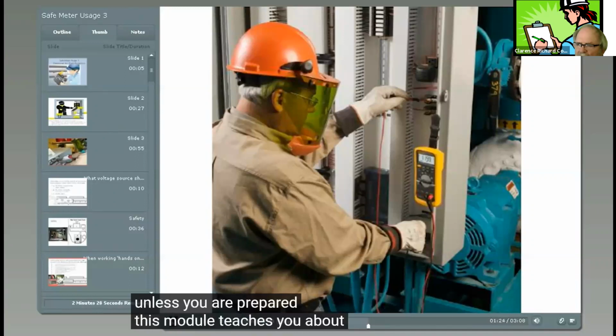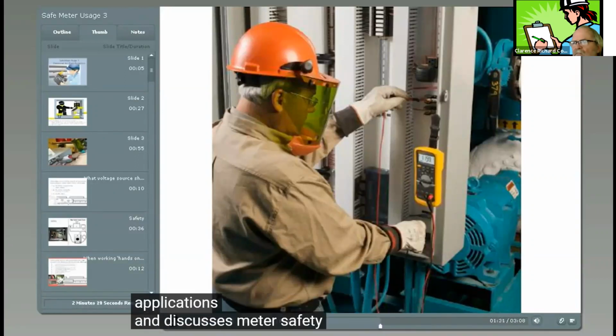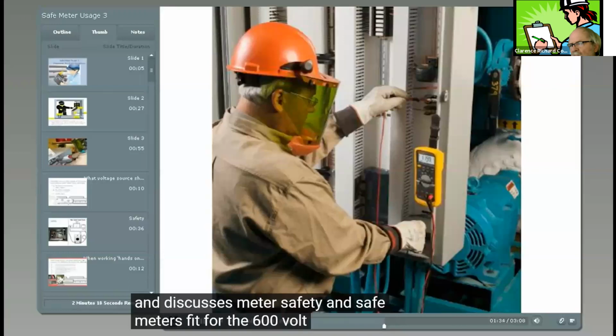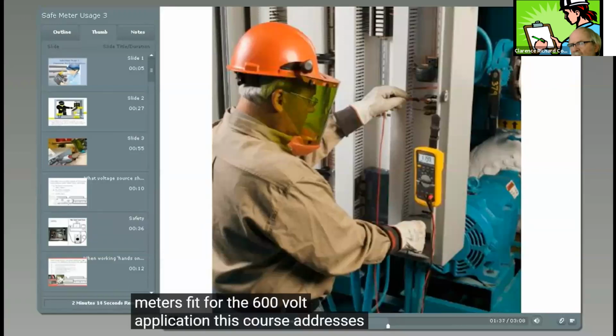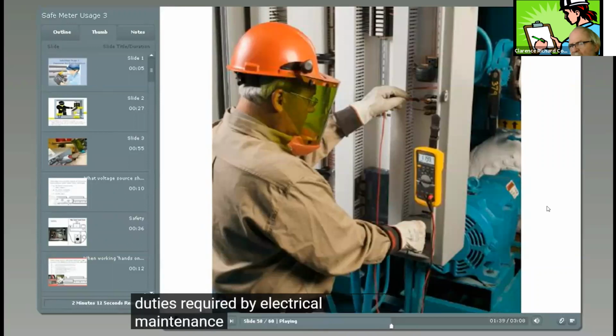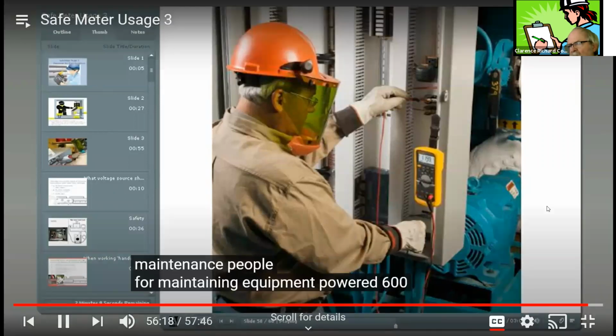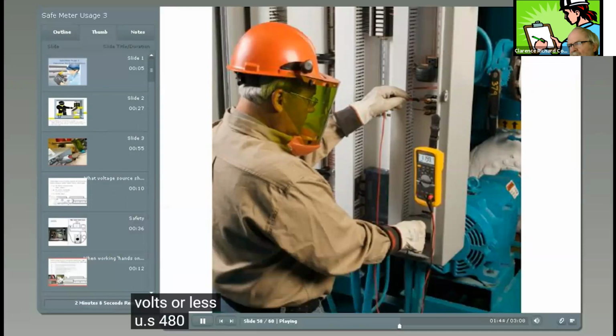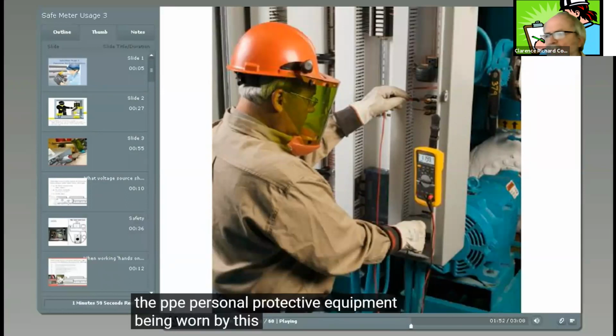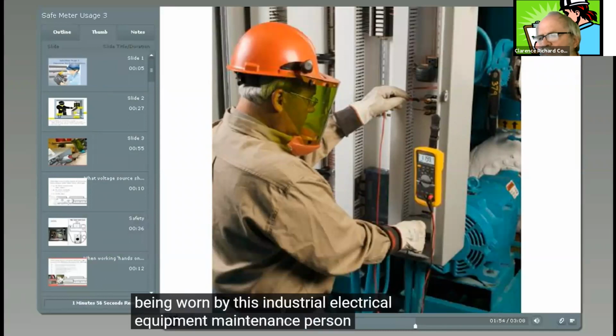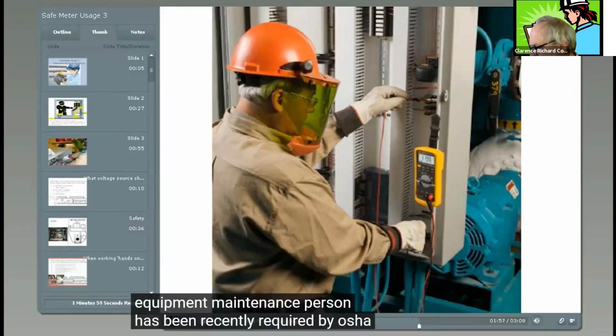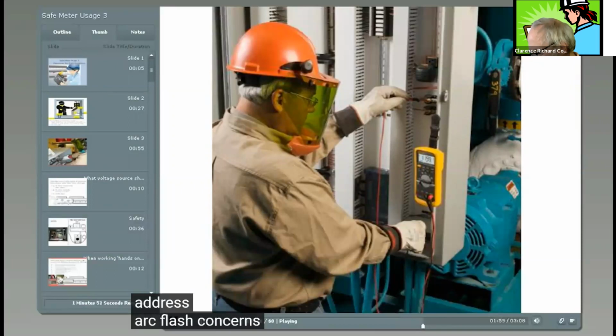This module teaches you about PPE, personal protective equipment, and using various meters in various applications, and discusses meter safety and safe meters fit for the 600-volt application. This course addresses the duties required by electrical maintenance people for maintaining equipment powered 600 volts or less, US 480 volt, electrical distribution systems. The PPE, personal protective equipment, being worn by this industrial electrical equipment maintenance person has been recently required by OSHA to address arc flash concerns.